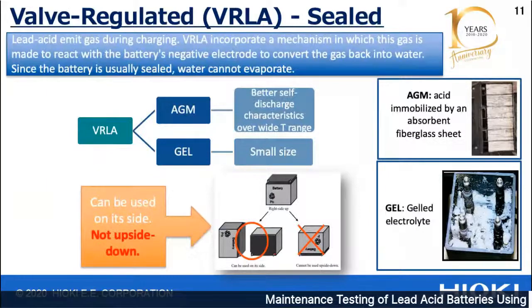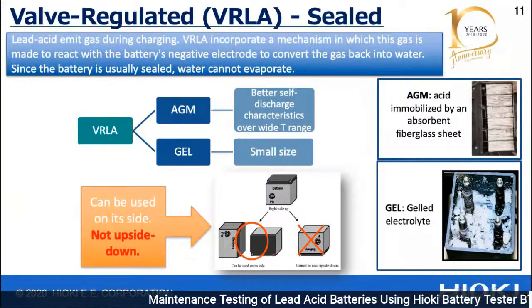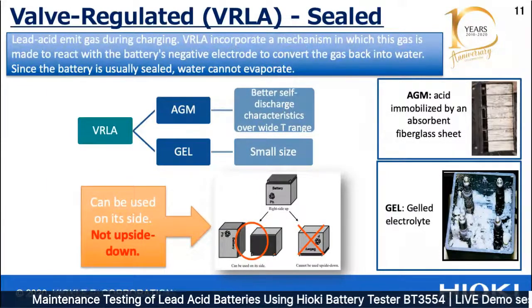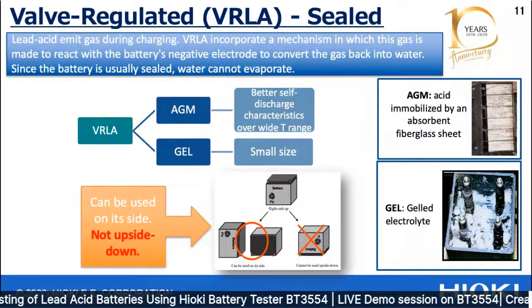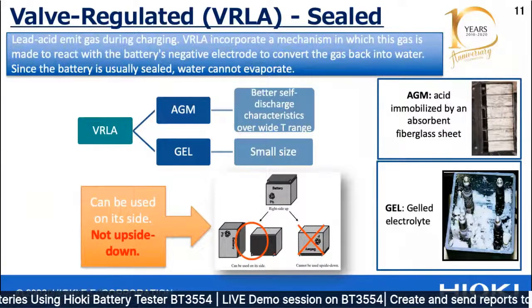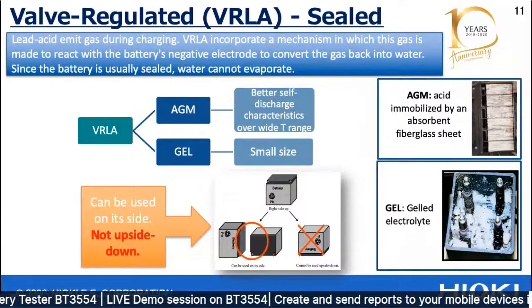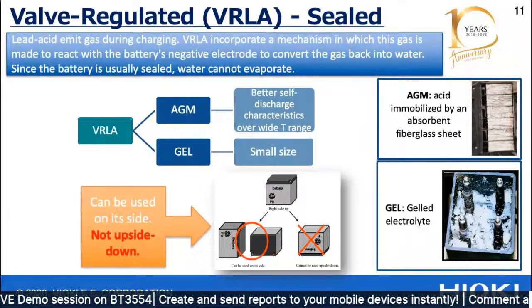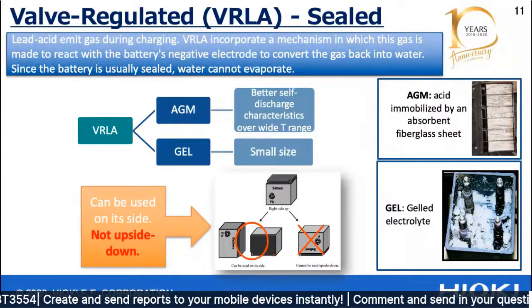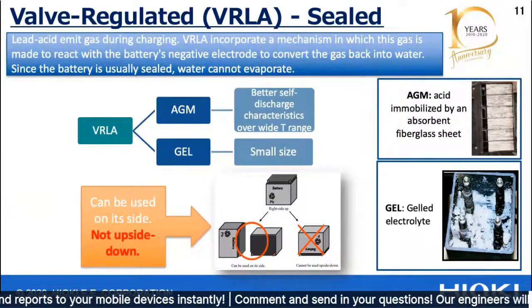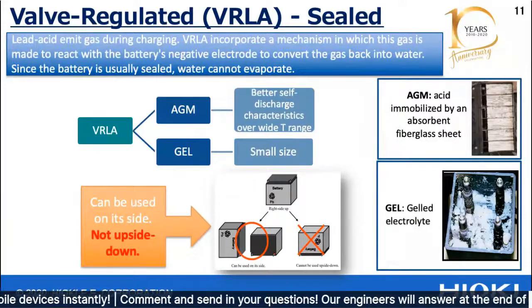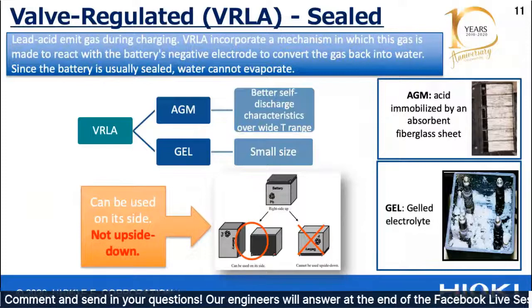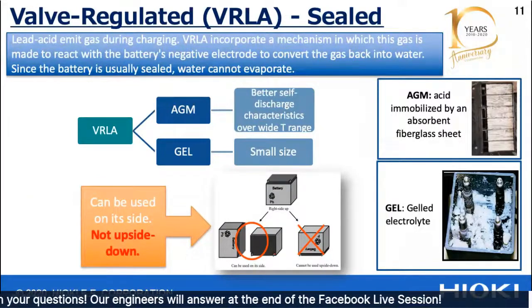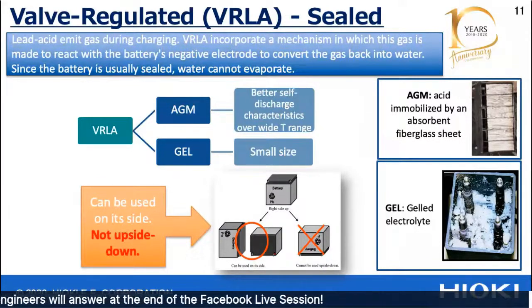Now, the next one is the valve-regulated lead acid, or VRLA, commonly known as the sealed lead acid type. This will emit gas during charging, but the VRLA incorporates a mechanism in which the gas is made to react with the battery negative electrode, converting the gas back into water. Because it is sealed, the water cannot evaporate, so it's contained inside. That's what makes it safe.